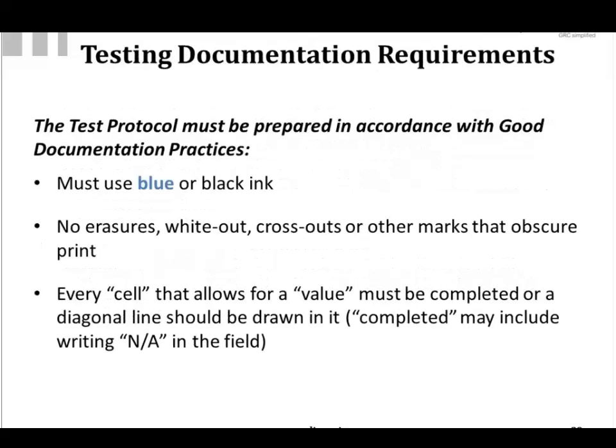So the test protocol and all of the results that you're capturing by hand always have to be done using good documentation practices. Now, you can do some of this electronically, but it's preferred that you do it by hand because it makes sure that everything is authentic.